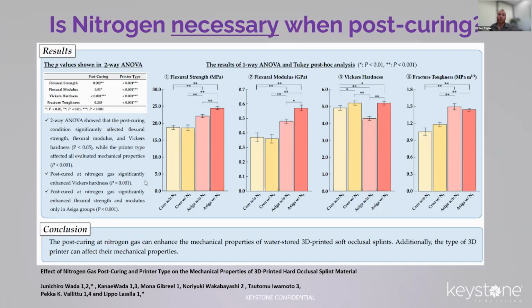When Keystone does all of our validation testing, we typically don't use nitrogen because we like to validate using a worst case scenario and to also show you and provide you that confidence that nitrogen isn't necessary, but it's always recommended for the proper and the best way to produce that end device.